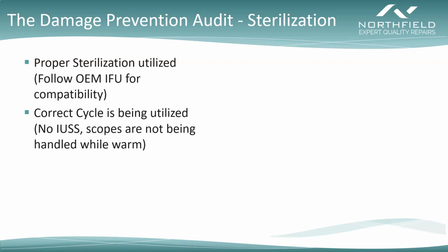IUSS, or immediate use steam sterilization, is particularly harsh on scopes because they have so many different materials that are tightly fit together, including glass and metal. Those material types heat up and cool down at different rates. And so if you use IUSS, which is a very rapid heat up and cool down process, or your scopes are being used as rapid turnover items, and so they're being taken while warm directly out of an autoclave into a very cool OR, that's going to cause those pieces to begin to separate from one another.